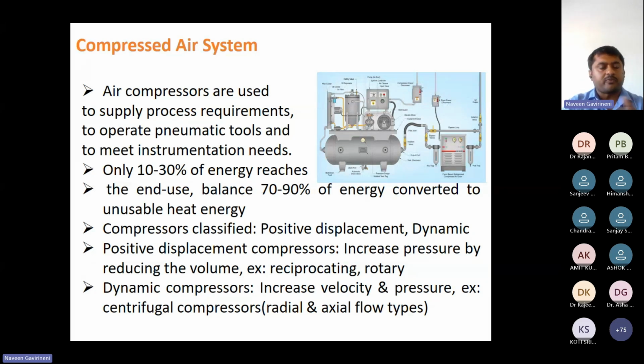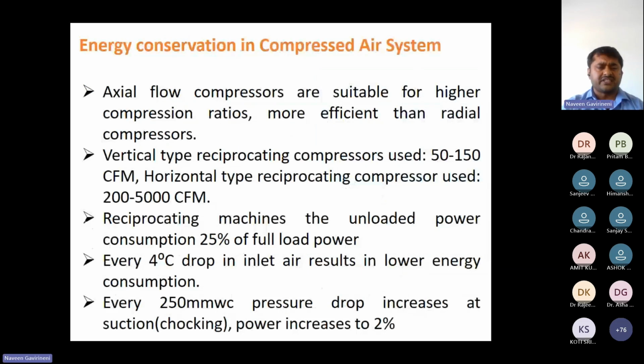Compressor classification: there are two types of compressors, positive and dynamic. So this is the energy conservation. The axial flow compressor is suited for high compression ratios and is more efficient than the radial compressor. Vertical type reciprocating compressors are used for 50 to 150 CFM. Horizontal type reciprocating compressors are used for 200 to 5000 CFM. From the energy point of view, for every 4 degrees of inlet air temperature, if the inlet air is less than the normal value, you will get less energy consumption. Why? Because there is a difference from loading and unloading.